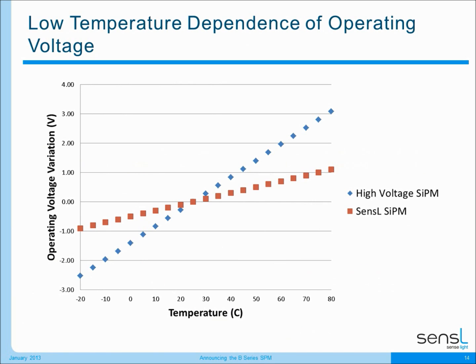Another area where SensL has created a very uniform device is in the low temperature dependence of our operating voltage. All silicon devices will have their operating voltage vary with temperature, and at SensL we've worked to minimize this effect so that as the temperature in our customers' systems changes, the output of our device varies as little as possible. I've shown here for a variety of temperatures how the operating voltage for SensL's silicon photo multiplier will vary, and I've compared and contrasted that to how the operating voltage for a high voltage silicon photo multiplier from other manufacturers will vary. You can see that we've really worked to minimize that for our devices, which can bring very good system benefits.